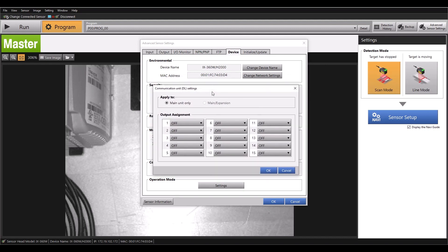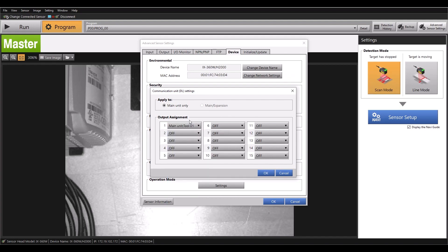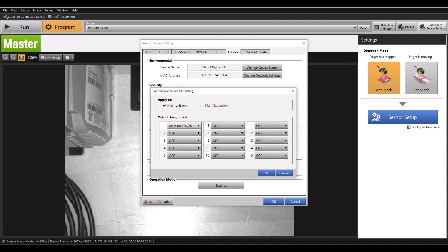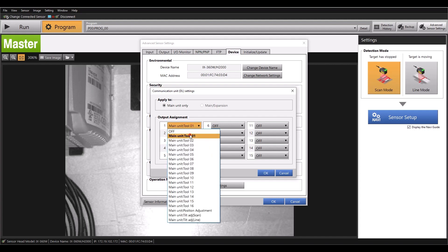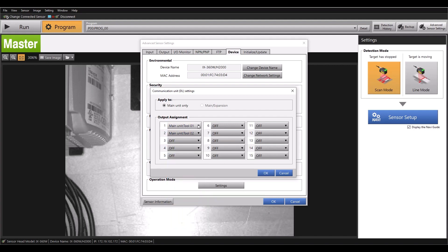This is an important section to adjust if you want to send measurement values for your tools. I just have a Main Unit Amplifier. If you have both a Main and Expansion Unit on the same DL unit, go ahead and select Main versus Expansion. Mine's simply grayed out because I don't have an Expansion Unit connected. Next, under this Output assignment, you need to tell the IX which tools you want to send measurement values for to the PLC. You can send up to 15 different measurement values, but in my program, I only have two tools, so I'm going to leave it as so and hit OK.